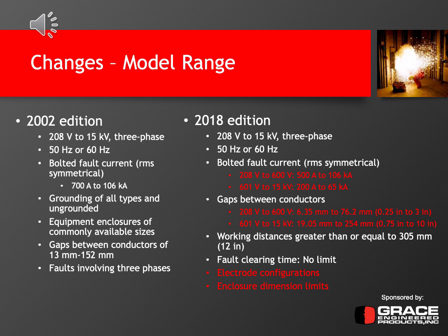And the gaps between the conductors have also changed. You can see the different ranges based on the red text between 208 and 600 volts, and then 601 volts and 15 kV, as compared to the 2002 edition. The working distances, again, are greater than or equal to 305 millimeters, so 12 inches. The fault clearing time didn't have a limit in 2018, and we've also added the electrode configurations and the enclosure dimension limits in this model.